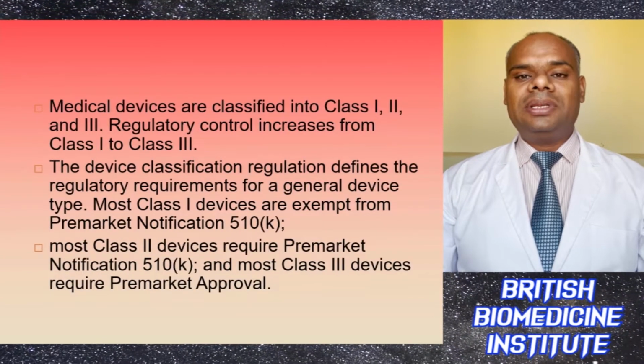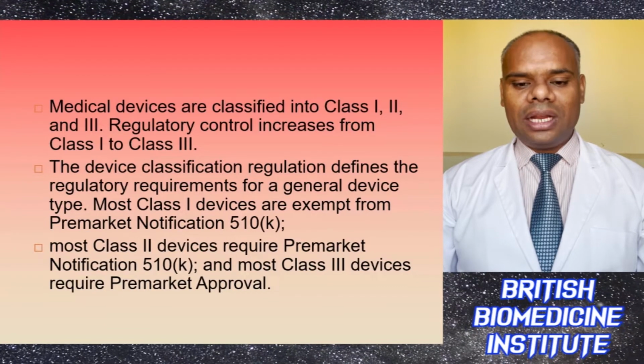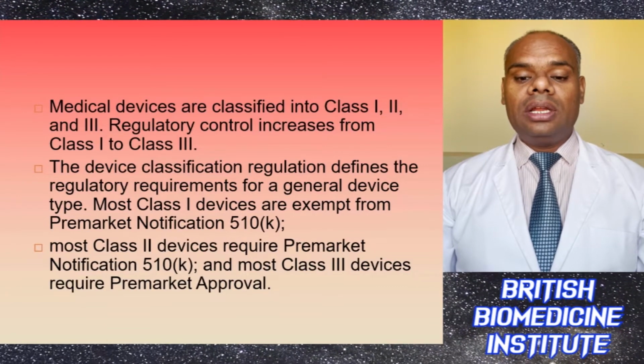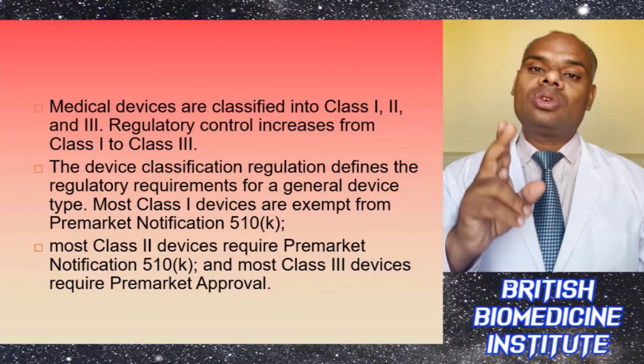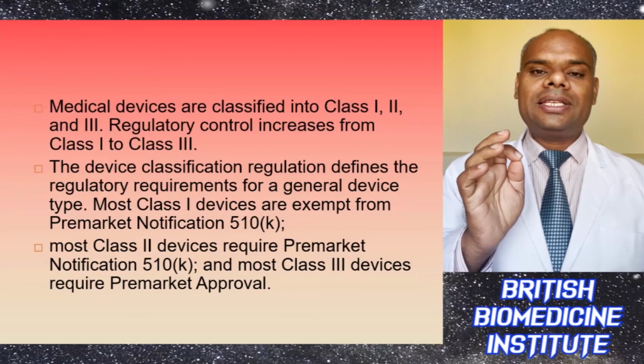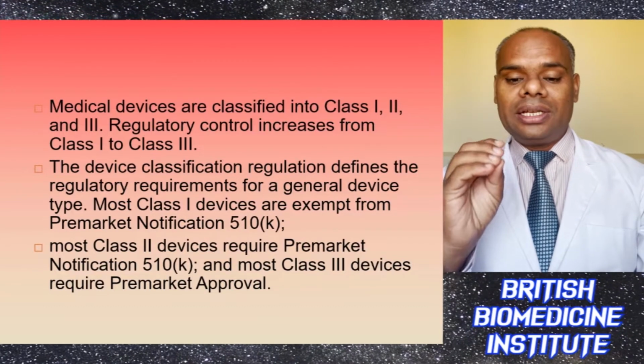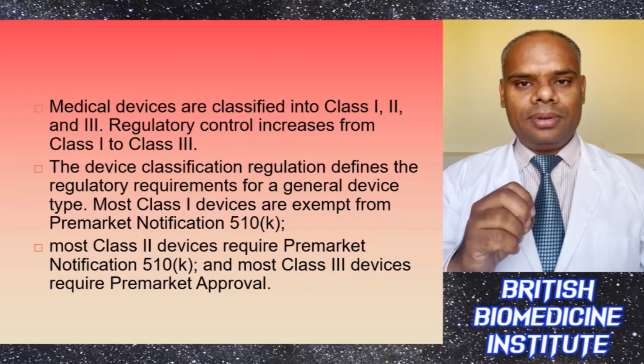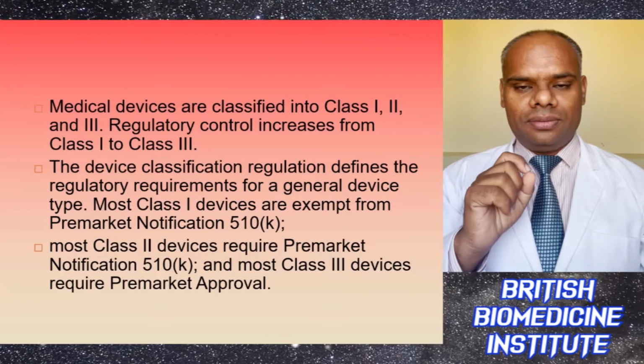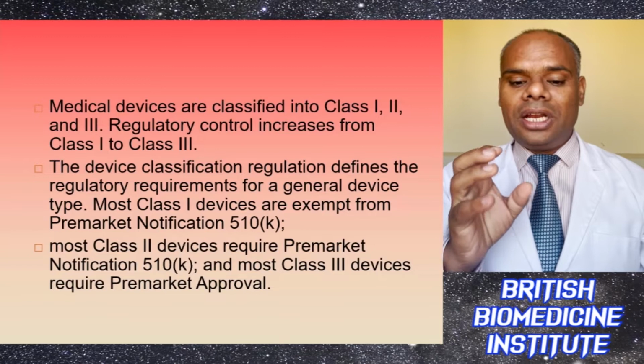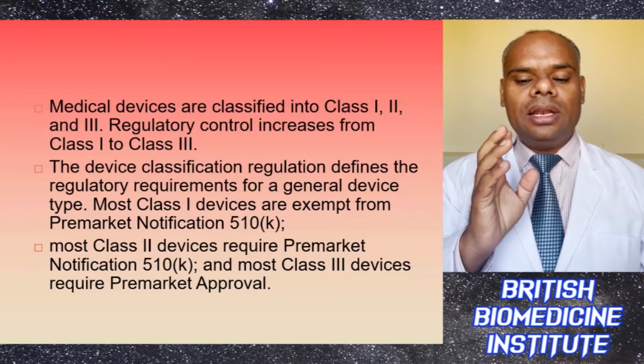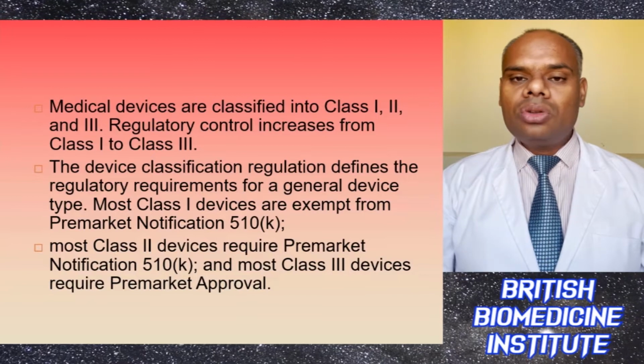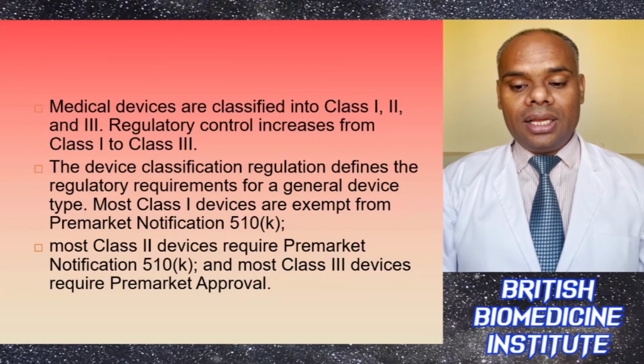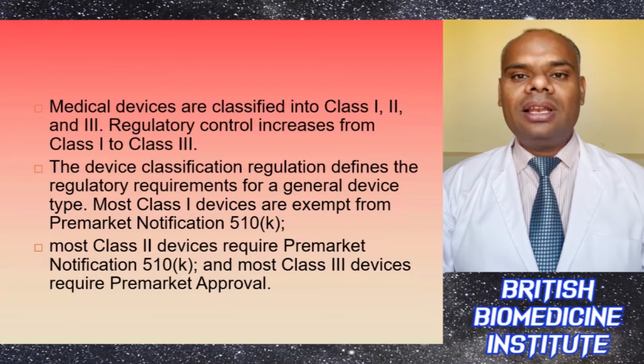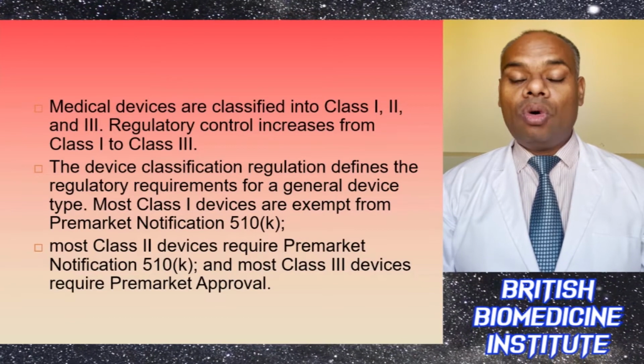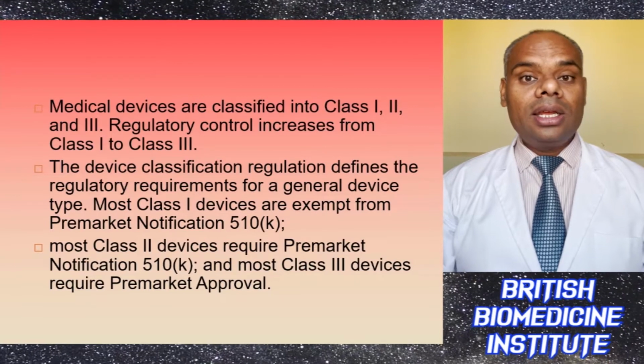So medical devices are basically classified as class 1, class 2 and class 3, and regulatory control increases from class 1 to class 3. The device classification regulation defines the regulatory requirements for a general device type. Most class 1 devices are basically exempt from pre-market notification, like 510K. Most class 2 devices require pre-market notification, 510K, and most class 3 devices require pre-market approval.